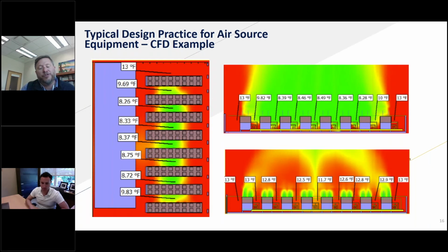So again, that's on grade. If we look at the unit below that, what we're actually considering there is that this unit is up on steel, meaning we have all the space underneath the units where we can actually pull in fresh air if we're not in a pit. We can pull fresh air in much easier, and even in a pit we could do it. And so now you can see we have almost eliminated, not quite, but almost eliminated the air recirculation from our discharge, because it's much easier to pull the air from underneath and from the sides of the unit than it is to have to pull it from it being thrown up and then sucked back in.